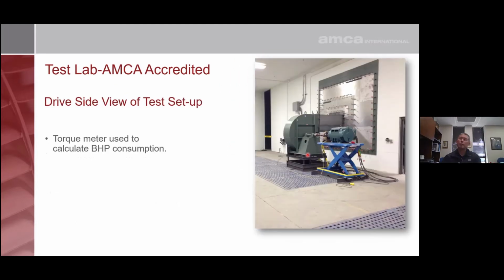On the drive side of the fan, we see a motor that's powering the fan. A lot of people think that that motor is what we also record energy consumption with, because technically you can sit there and take voltage readings, you can take an amp reading. If you have a motor data sheet, you'll have an efficiency and a power factor that you can do a calculation with. But unfortunately, unless that motor is calibrated along with the VFD for the specific speed that the fan's running at, as well as the load conditions, those numbers are just estimates. They're not guaranteed numbers. Your horsepower calculation will be off by as much as 5 to 8 percentage points. Most fan manufacturers utilize a torque metering device, such as a torque meter, to record the energy or the work that the fan does, and it's much, much more accurate.